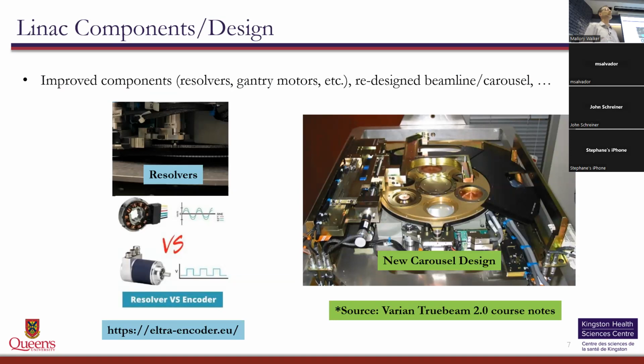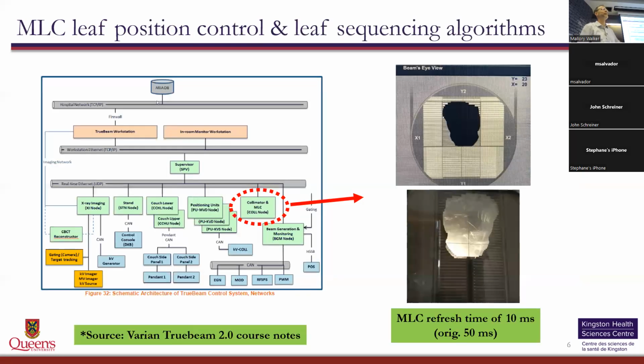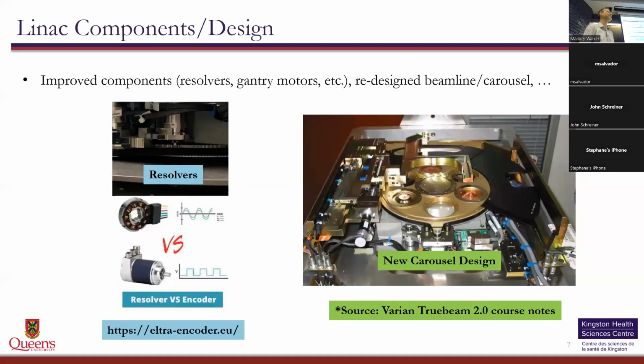A lot of the components have been switched over. We have resolvers everywhere, which allows us to get sub-millimeter precision on all of our positions. And to do it reliably, we used to use optical encoders where it would spin around and read the optical side of things. The carousel has been redesigned so that when we're delivering different energies of beams, it's a new process. It does mean that every time you deliver a beam, it runs through a whole series of checks, and therapists don't like that because it's a 30-second delay as it's making sure everything is perfectly right.